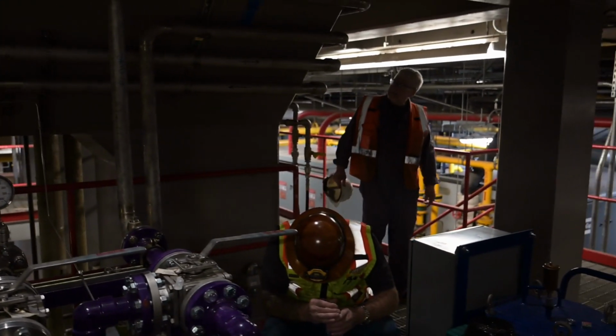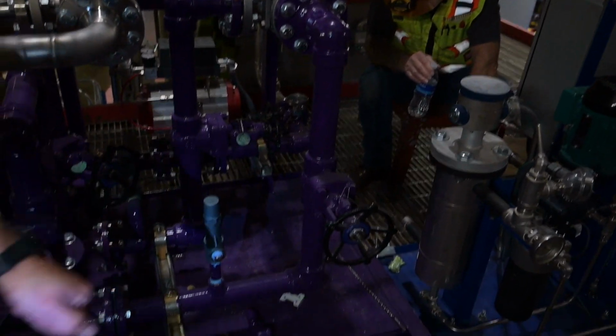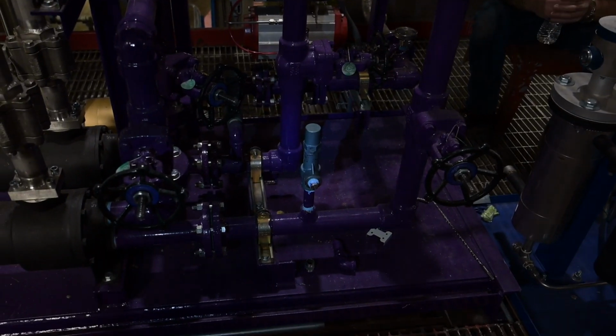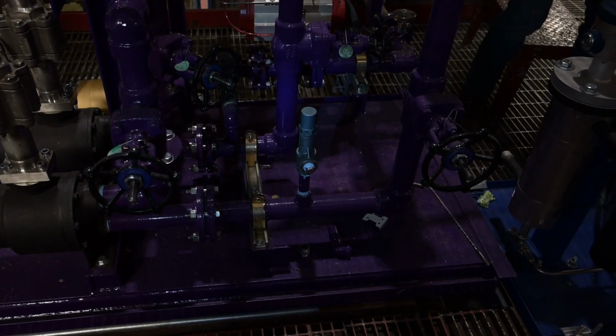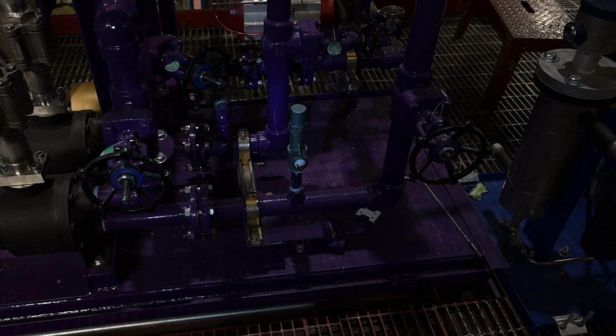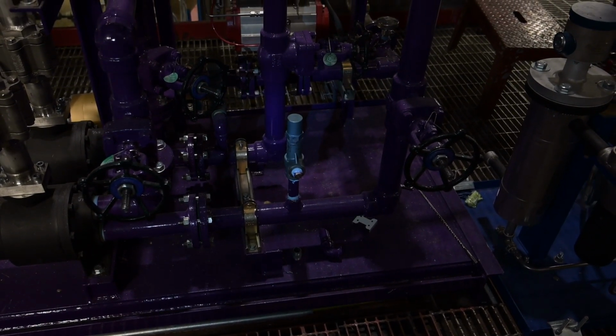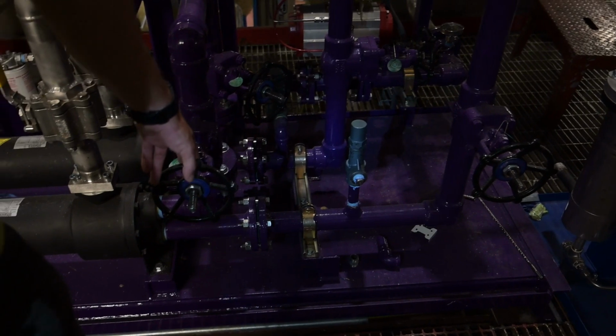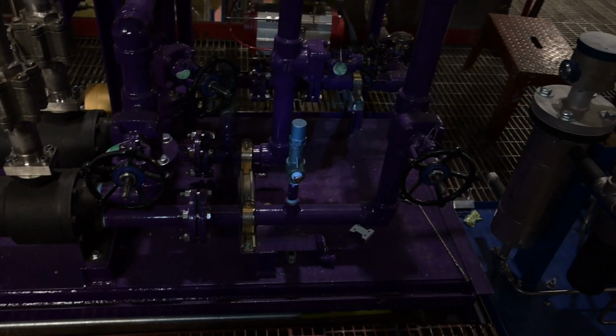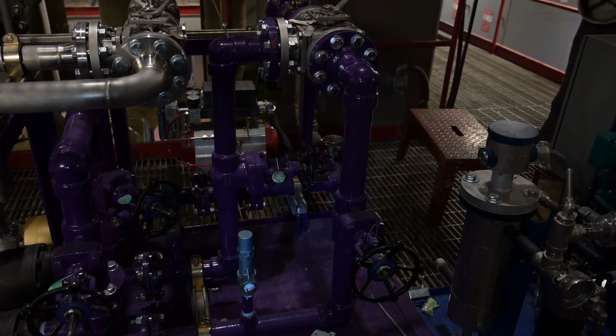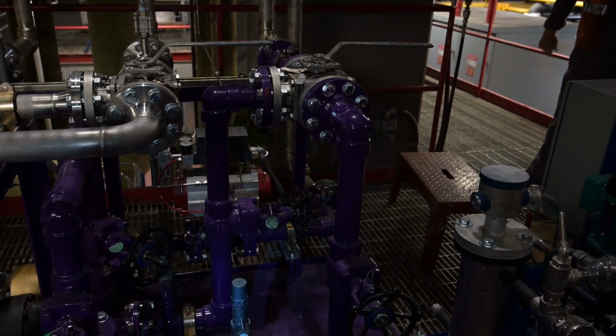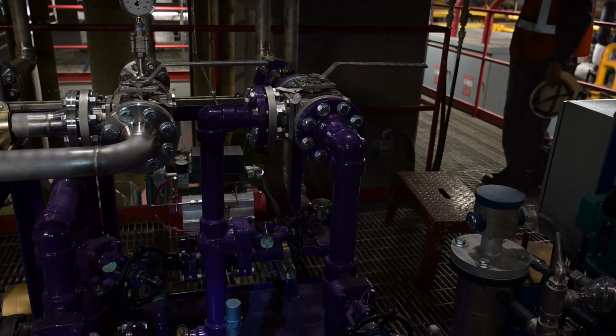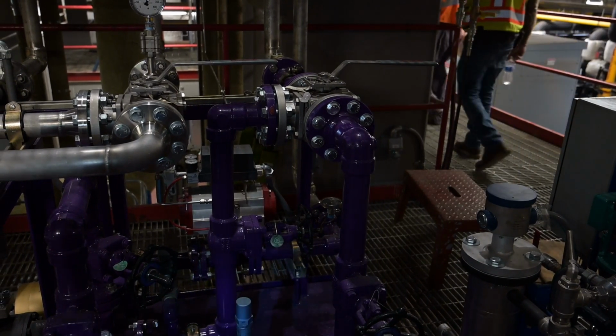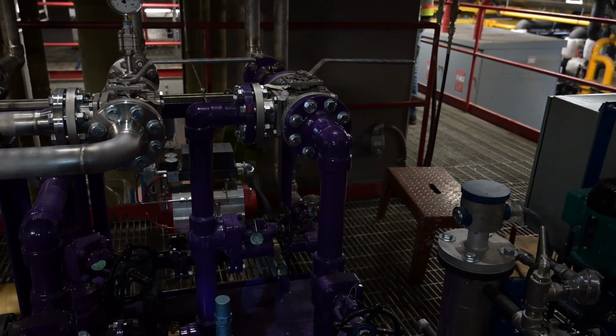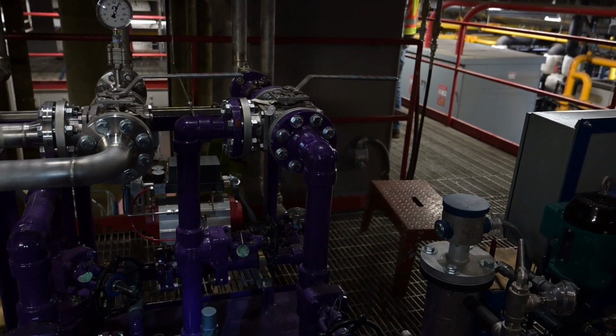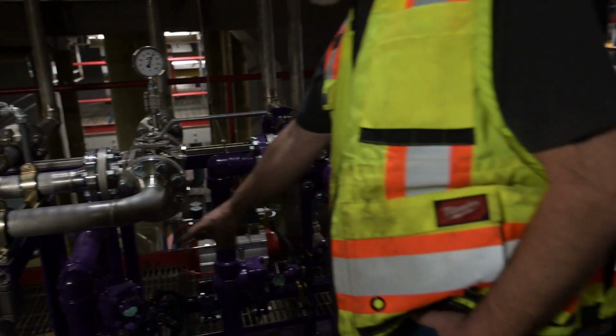We've got these two small relief valves. Those are thermostatic relief valves. Their purpose is to protect the heat exchangers in the event where the water isolation valves have been closed off and lube oil is running through the heat exchanger, causing the water to heat up and expand thermally. We want that water to have somewhere to go, so it goes out the relief valve. But yep, so this one is online.